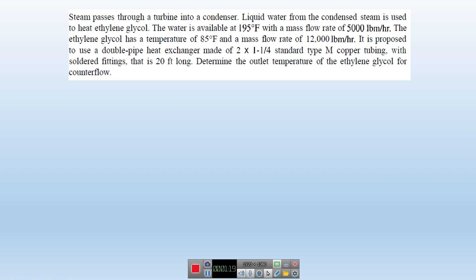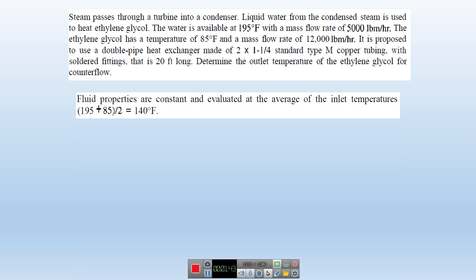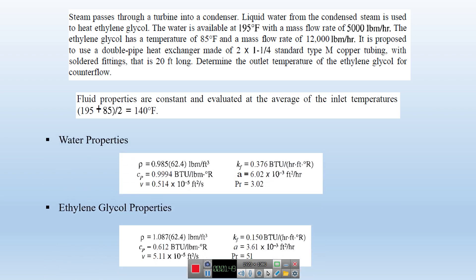To design any heat exchanger, the first step is to find thermophysical properties. To find these properties, you need a reference temperature — normally the average of inlet and exit temperature. Here, both exit temperatures are unknown, so you can start from the inlet temperature, calculate the average temperature at the inlet, and use that to find thermophysical properties.